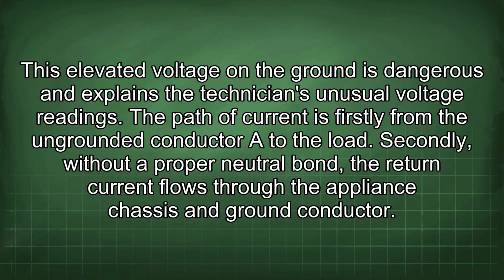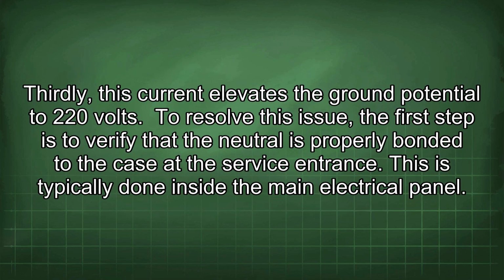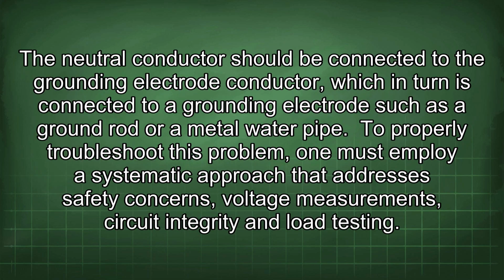The path of current is, firstly, from the ungrounded conductor to the load. Secondly, without a proper neutral bond, the return current flows through the appliance chassis and ground conductor. Thirdly, this current elevates the ground potential to 220 volts. To resolve this issue, the first step is to verify that the neutral is properly bonded to the case at the service entrance. This is typically done inside the main electrical panel. The neutral conductor should be connected to the grounding electrode conductor, which in turn is connected to a grounding electrode such as a ground rod or a metal water pipe.